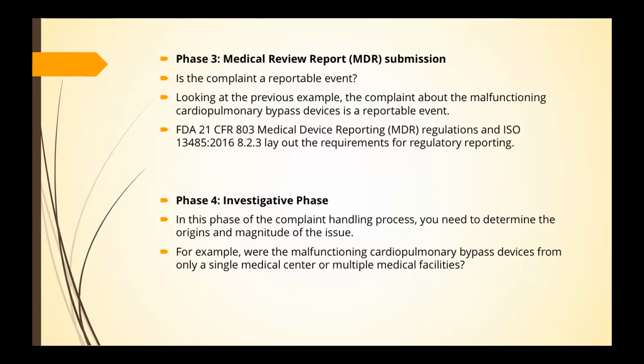In this phase, they need to determine the origin and the magnitude of the issue. Also, for example, taking the same example of cardiopulmonary bypass, whether it has happened only in a single medical center or they have received several complaints of that particular device from different medical facilities. Other than that, in the investigation phase they look at the design, development and all the different phases, and they use all their risk management files to identify whether this complaint can be added into trend reporting, or whether it can be used as feedback to have a better product in the market, which ensures patient safety.